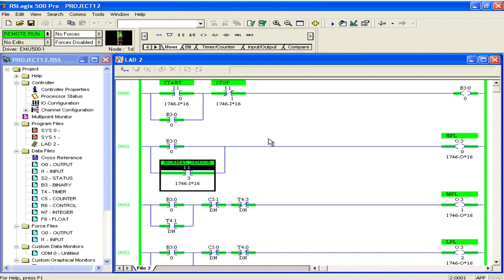If there is a normal condition, then all the loads will be on. If any fluctuation or overload occurs, at that time the low priority and medium priority loads will get off sequentially, and we make sure that the high priority load stays continuously on. And when there is a normal condition, with no fluctuation and no overload, all the loads will again get on.